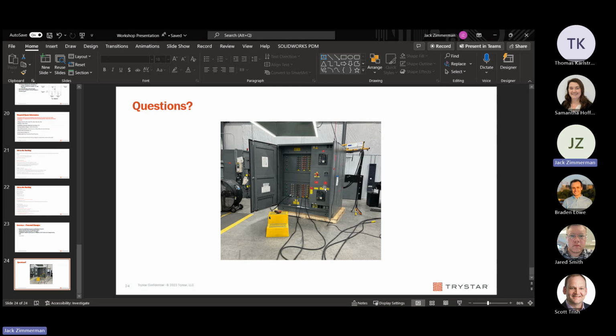Okay. So I want to clarify that just the control panel, when you go into it, has some voltage present, but the unit itself doesn't pose an additional arc flash hazard compared to any of our pad mount units that are the same rating, because that's determined based off of your available fault current, and this won't have any more available fault current than your standard pad mount. So if there is a consideration for needing that labeling, it would be across our entire pad mount line, if that makes sense. How much would a customer have to get inside that control panel once it's installed?